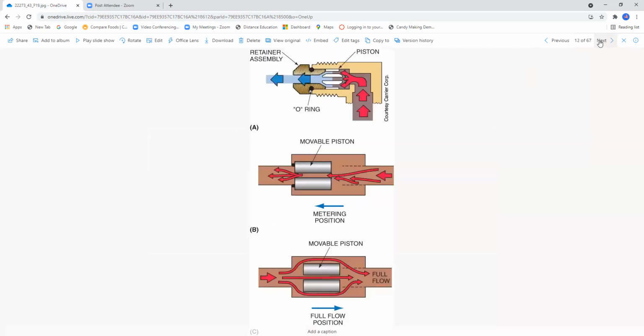Now we're talking about the pistons. This is found on page 1284, figure 43.19. This piston basically acts as, if I'm not mistaken, is this the one that has the check valve in it? So when the flow is reversed, yeah. And then basically this serves two purposes. It restricts the flow of refrigerant from high pressure to low pressure, and it also acts as a check valve.